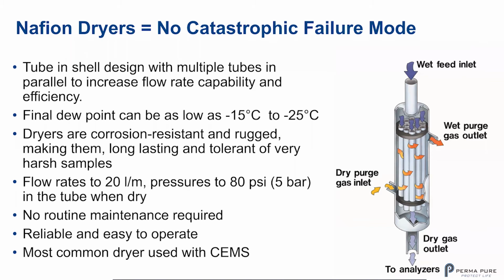The multiple tubes in parallel increase the flow rate capability and efficiency. We have final dew points that can be as low as -15 to -25. The dryers are corrosion resistant and rugged, making them long lasting and tolerant of very harsh samples. We have flow rates to 20 liters a minute and pressures to 80 PSI. Again, no routine maintenance required, reliable and easy to operate. And this is really the most common dryer used with CEMS because of the flow rates.